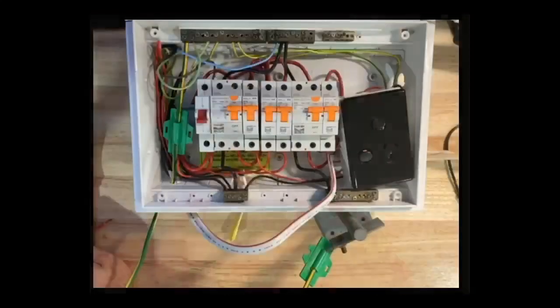that are connecting from the earth bus bar in my switchboard out to extraneous metal parts, as we call them, other metal things that are in the installation, like steel benches, copper pipes, things like that. Those typically need to be connected to our earthing system as well. So part of our earth continuity testing is to test that. Let's have a quick look at what we are going to do.